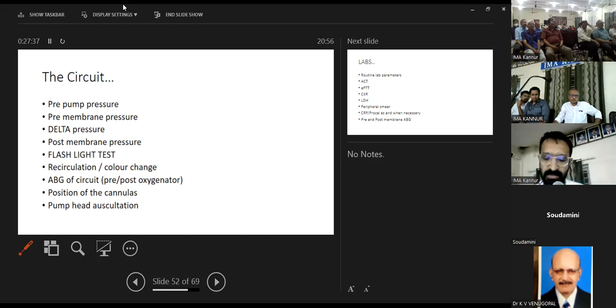ABG from the circuit, position of the cannulas, and pump head or auscultation. If there is any bubble trap, you will hear it on auscultation. The labs, the routine lab parameters like the CBC, RFT, LFT, which is checked daily. The ACT, as I told, is done 4th hourly. APTT, twice daily you do it. And if the ACT and the APTT do not match, then you have to do it more frequently.